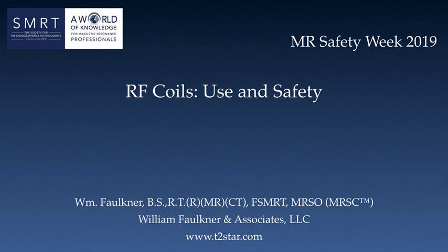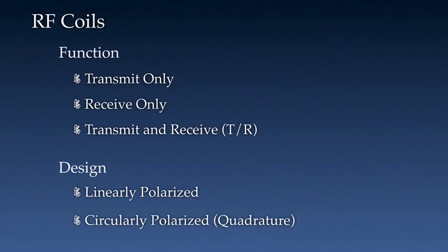RF coils differ in both their function and design. With regard to function, some coils only transmit RF, while others only receive. Some coils may be configured to both transmit and receive radio frequencies. The design of the coils is that they are either linearly polarized or circularly polarized, also known as quadrature.